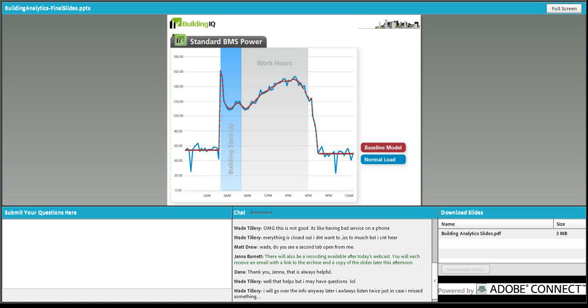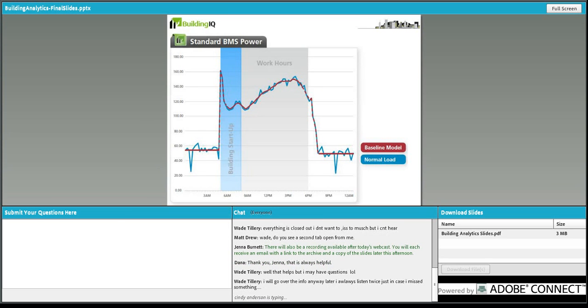Also shown on this graph is a baseline model, where through knowledge of all those underlying systems we can very accurately know what the power use is going to be. That's quite useful on its own as part of our measurement and verification—we can monitor times when the system operates without BuildingIQ control, and develop a standard operating profile for the building. But where it gets really interesting is when we look at the degrees of freedom.